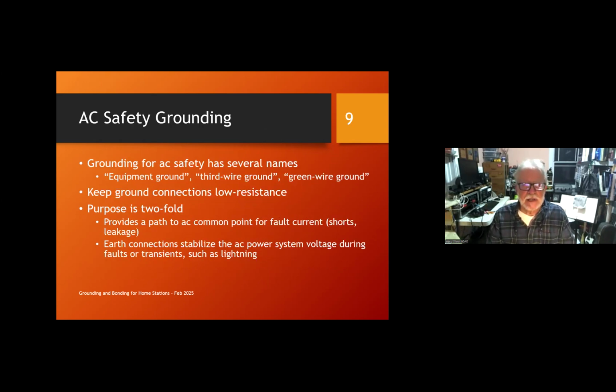Let's jump to AC safety ground. Grounding for AC safety has several names depending on where you are in the country and how old your electrician is. The current standard wording is equipment ground, and that's what's meant by the green wire or the third wire. It's a connection between the metal enclosure or any exposed metal on a piece of equipment and the reference point inside your AC distribution system.